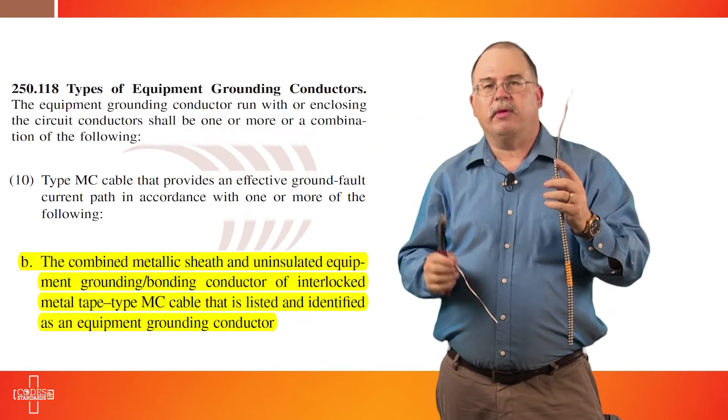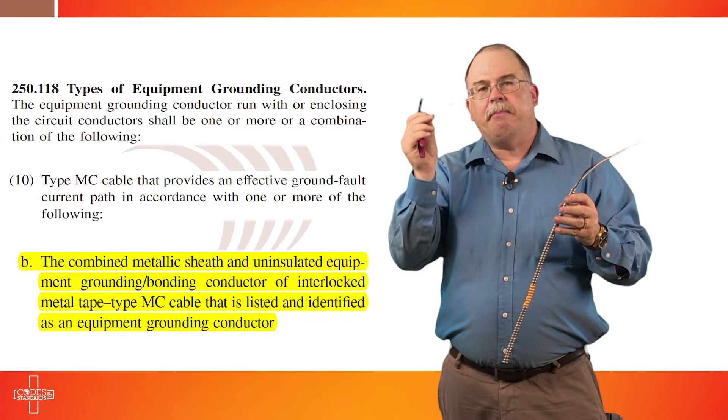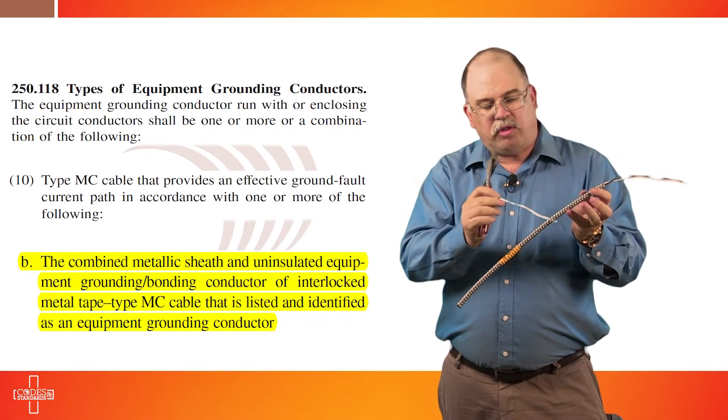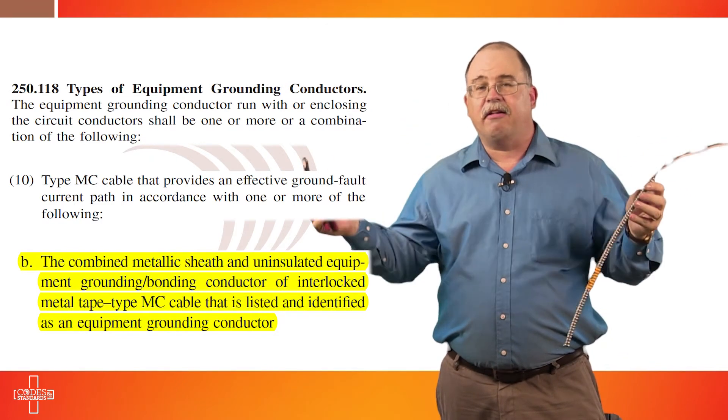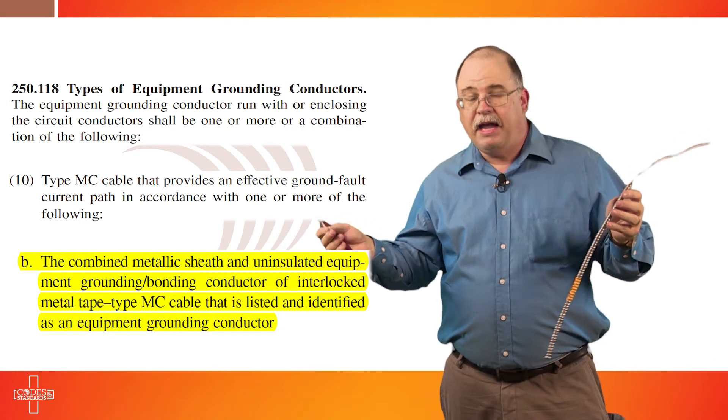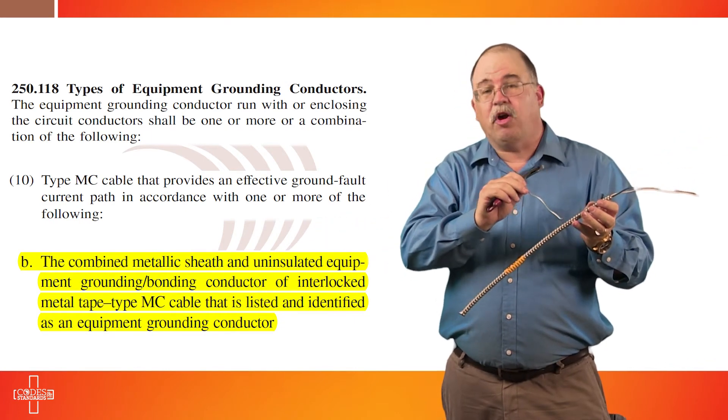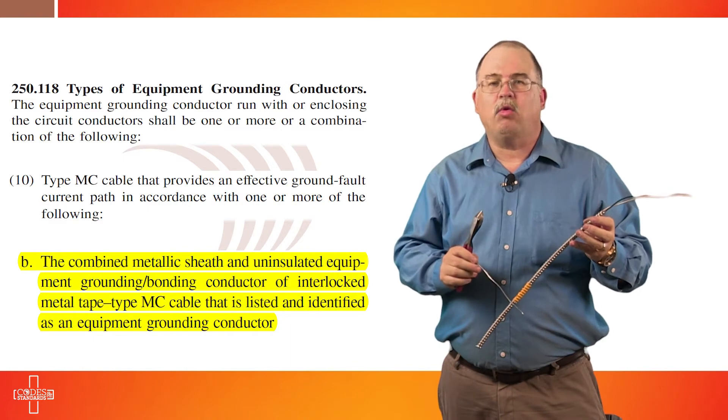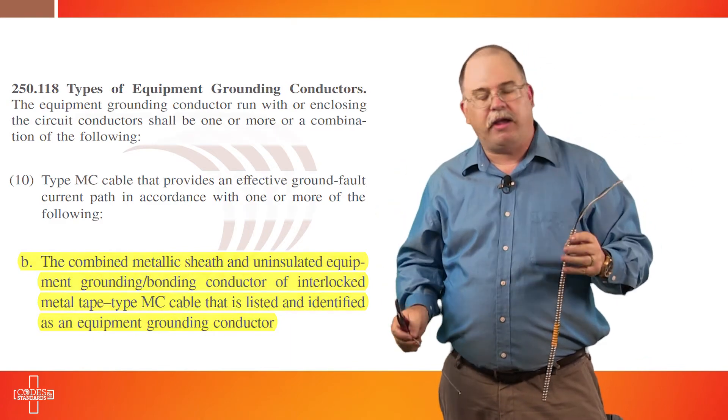The aluminum grounding and bonding conductor makes intimate contact with all of the convolutions through the entire length of the cable. In that way it is now an effective ground fault current path and will serve as an equipment grounding conductor in this type of product.